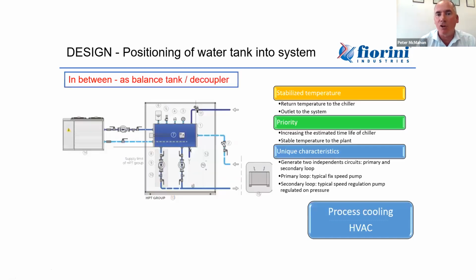However, there is a third option, and this is by far the most common solution that most people would use. So what we do is we put the buffer tank in the middle, basically as a decoupling tank. So we have a primary loop where the chiller is pumping out through the buffer tank and back into the chiller again. Secondly, we're coming off the pumps, and that's basically pumping down to whatever it happens to be, whether it's HVAC or process cooling. But again, you get a very stable temperature going out and coming back.